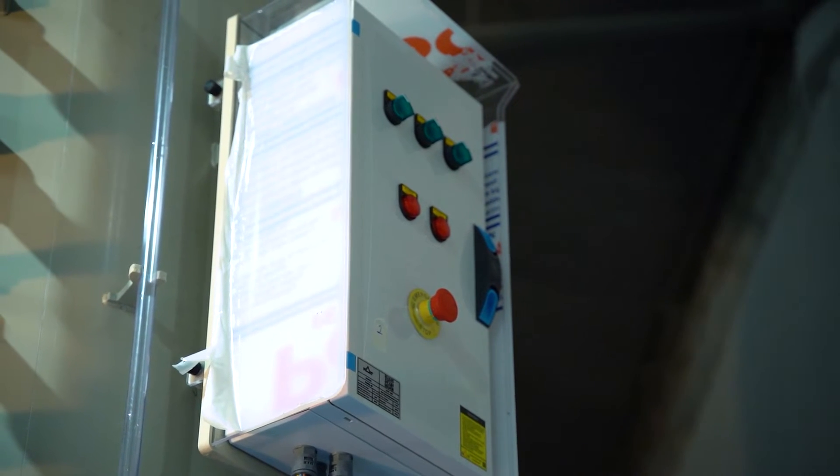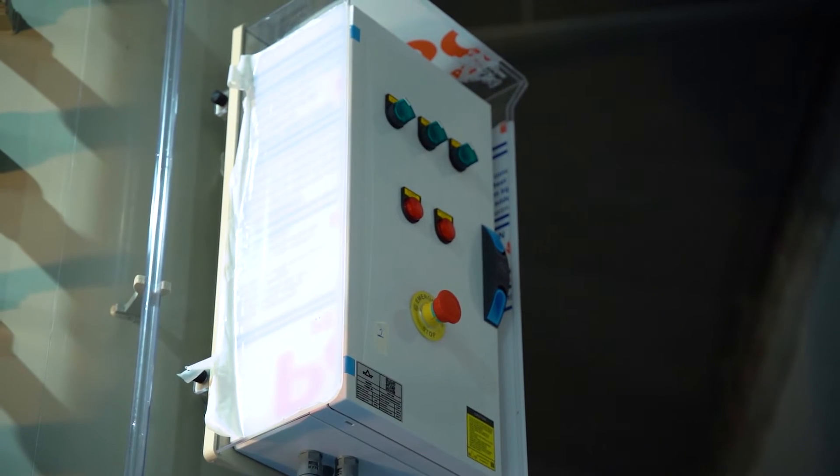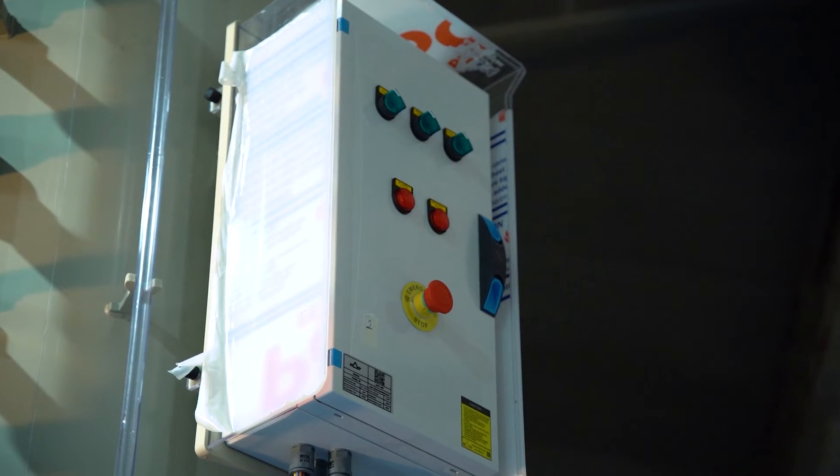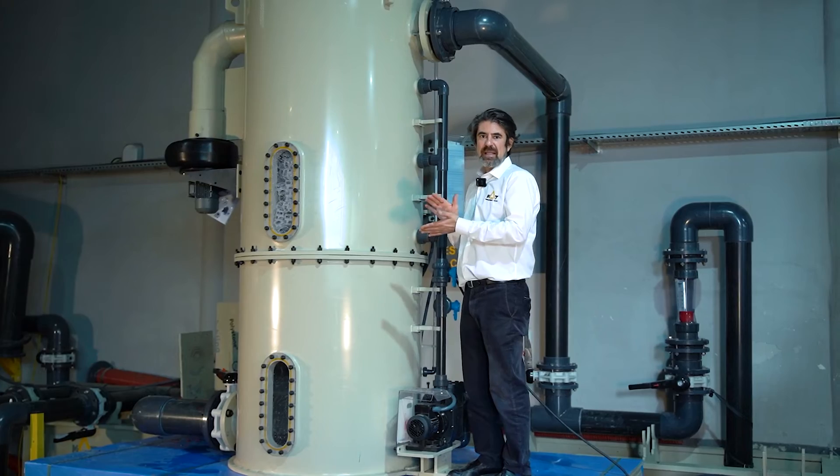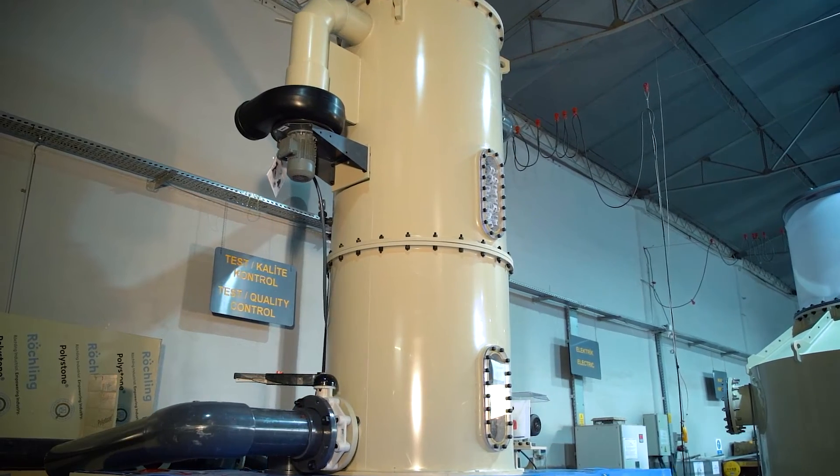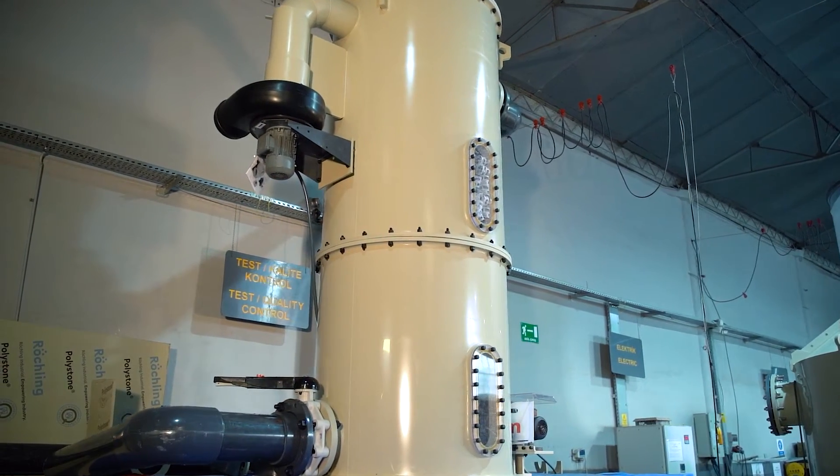Depending on the load, every day, once a week, or once a month, it's possible with our PLC and control units to run this pump autonomously, make a backwash inside the system, and get rid of all residues. This small unit can process 100 cubic meters per hour.